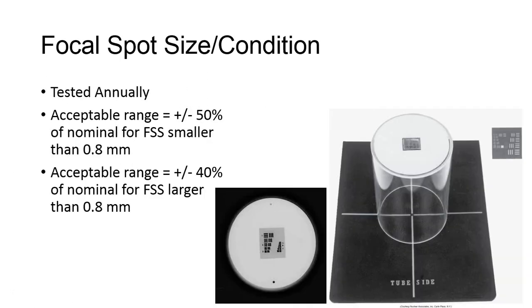When a new x-ray tube is installed, the actual focal spot sizes for large and small focal spots are rated nominally and typically recorded on the outside of the x-ray tube housing. There's a lot of lenience for accuracy here, due to the complicated nature of the tube construction and multiple factors affecting beam geometry. A baseline reading should be taken and archived when every new x-ray tube is installed for comparison to annual tests, or if testing is needed between annual recommendations when a loss in resolution may be visibly noticed suddenly.